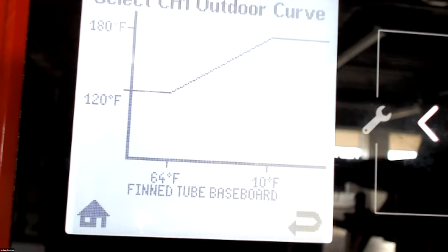This curve doesn't meet a lot of our demand for what we have in our market. So number one, the 10 degree design, that means that at 180 degrees, this thing will be running at full potential, 180 at 10 degrees outside. Most houses, I can state in New England, when they designed them and laid out the baseboard in the house, they put just enough baseboard, 540 BTUs per foot, into that house to heat it. They put the minimal amount, all right? They didn't put extra, but the minimal amount. So when we look at these curves and we set it, we want to try to cool it down, but if you go up in the house, there's a good chance they got furniture in front of half the baseboard or a good chunk of it. So every foot, 540 BTUs, we got to take that out of the equation. So we can't drop too much.